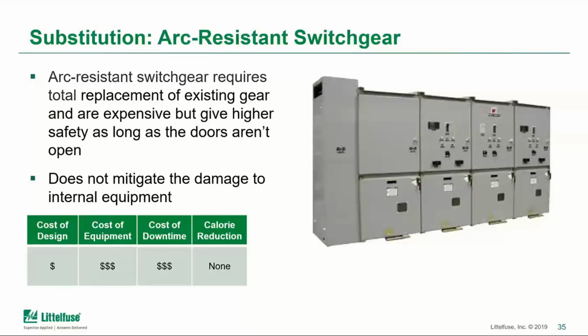The cost of the equipment, however, is fairly high, including the equipment itself as well as any modifications potentially made to the building. The cost of the downtime is also fairly significant, as if there's an arc event, there would have to be rebuilding of the equipment containing that gear, as it's not providing a reduction to the incident energy. And so that's one of the reasons why this isn't mentioned as a 240.87 method, as it's not specifically reducing the incident energy value.